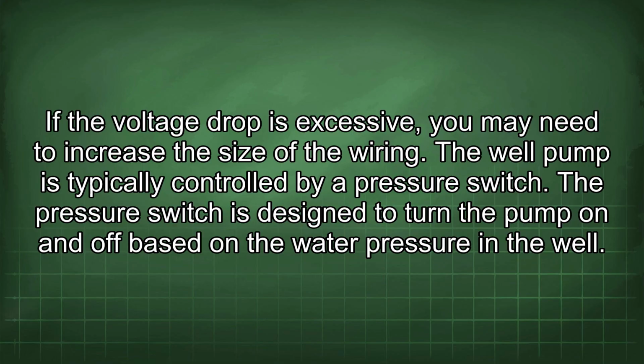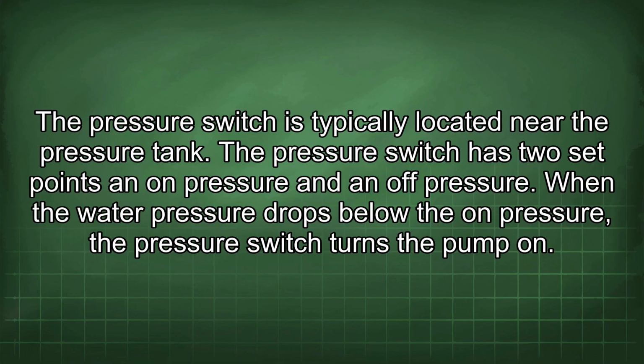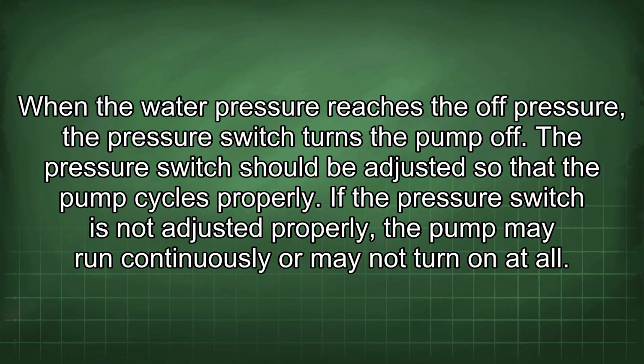The well pump is typically controlled by a pressure switch. The pressure switch is designed to turn the pump on and off based on the water pressure in the well. The pressure switch is typically located near the pressure tank. The pressure switch has two set points, an on pressure and an off pressure. When the water pressure drops below the on pressure, the pressure switch turns the pump on. When the water pressure reaches the off pressure, the pressure switch turns the pump off. The pressure switch should be adjusted so that the pump cycles properly. If the pressure switch is not adjusted properly, the pump may run continuously or may not turn on at all.